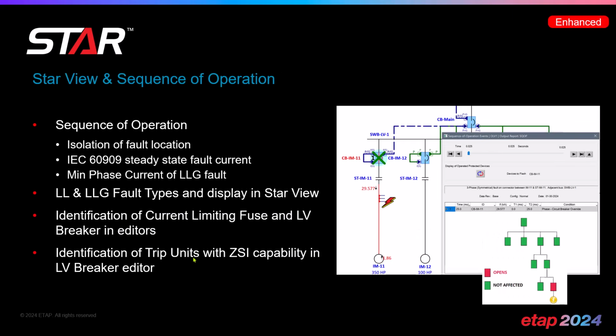We've also enhanced the Star view as well as the sequence of operation by allowing you to display various additional fault types such as line-to-line and line-to-line-to-ground fault types that you can display in the Star TCC. And you can also perform identification of trip units with the ZSI capability inside the low voltage circuit breaker. And you can also identify the current limiting fuses and low voltage breakers directly within the editor, essentially allowing you to quickly find devices that have ZSI capability before you select these devices for your protection and coordination purposes, allowing you to again make the correct design choices with efficiency and speed.